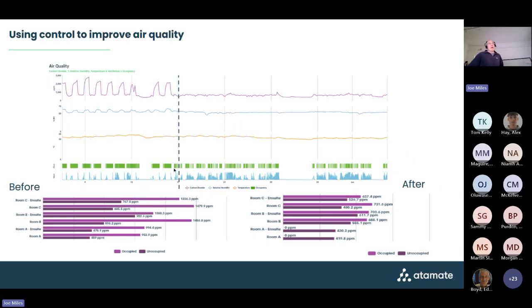And we've got a before picture. Again, the lighter coloured purple is showing the occupancy air quality, and the darker is the unoccupied. You can see that we're around 1100, 1200 parts per million before the dotted line. When we take control of the building, we flatten out the line, and occupancy is broadly the same. Obviously a bit of a gap here, but the air quality drops to around 600 parts per million, something like that.